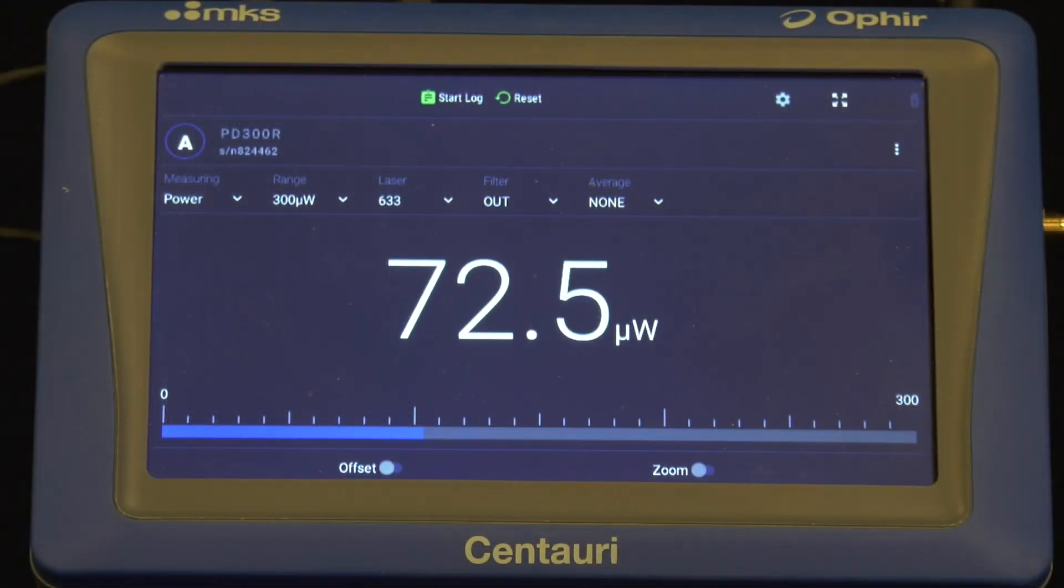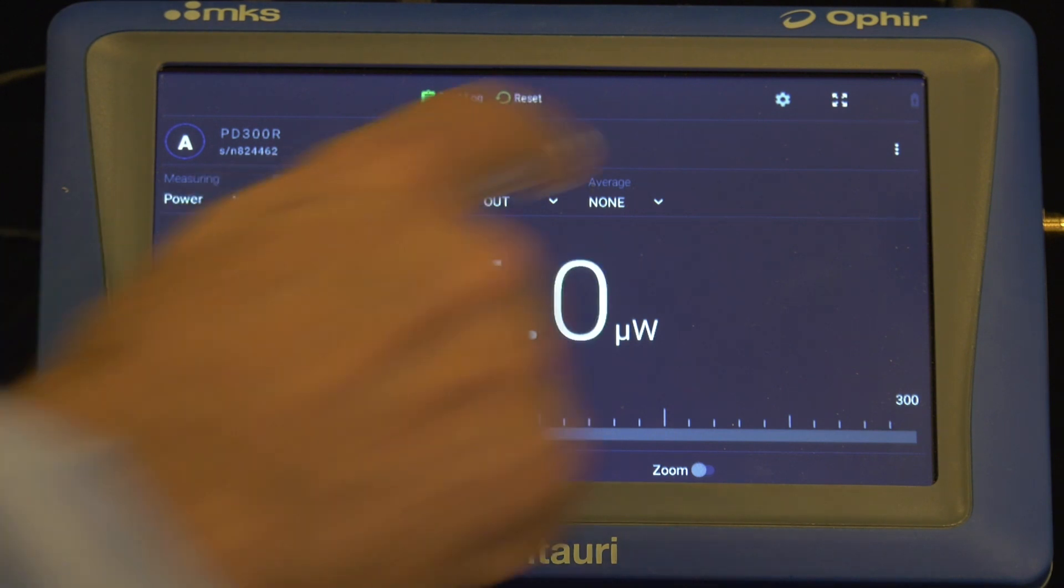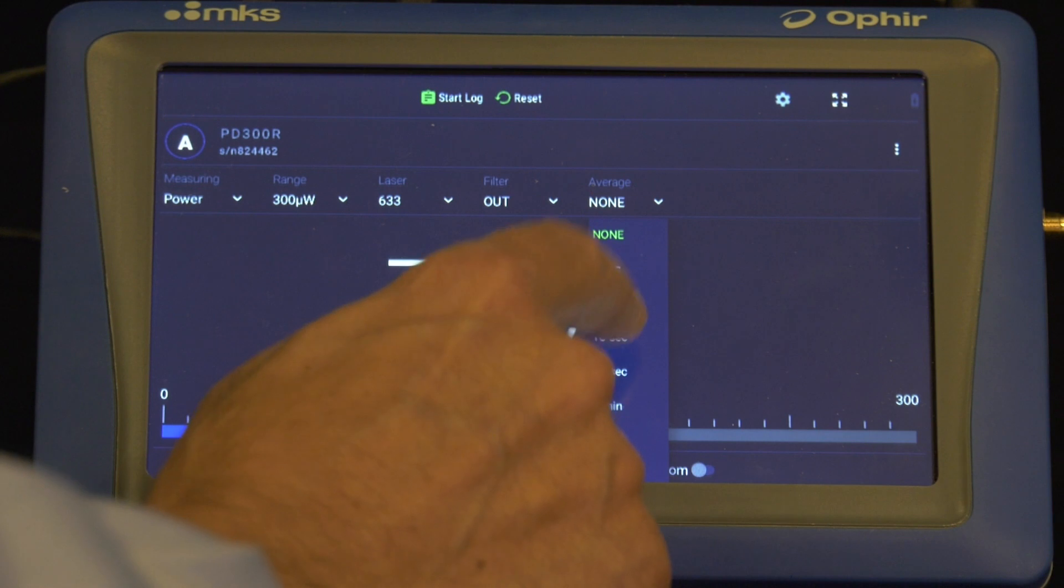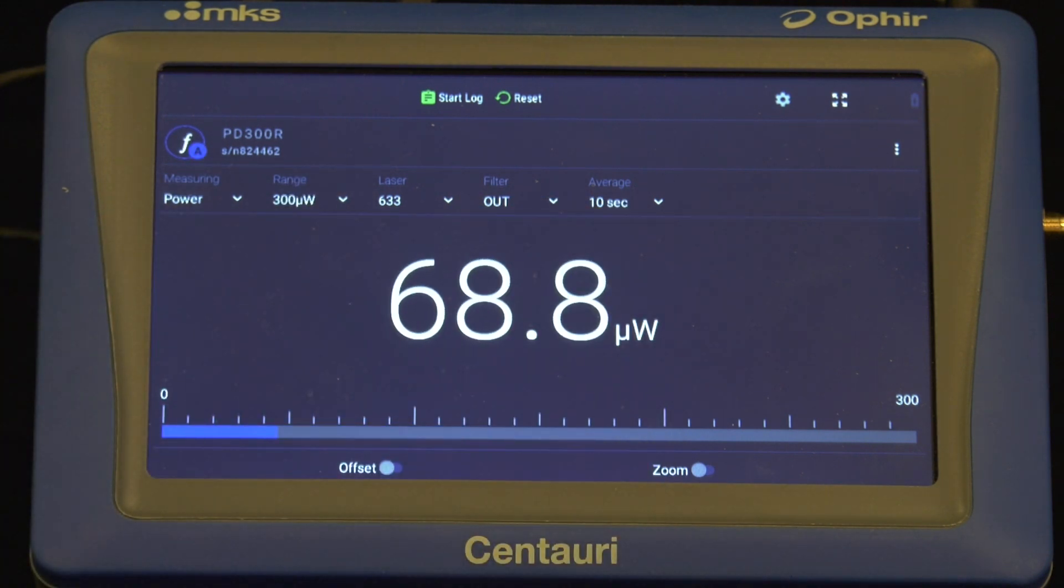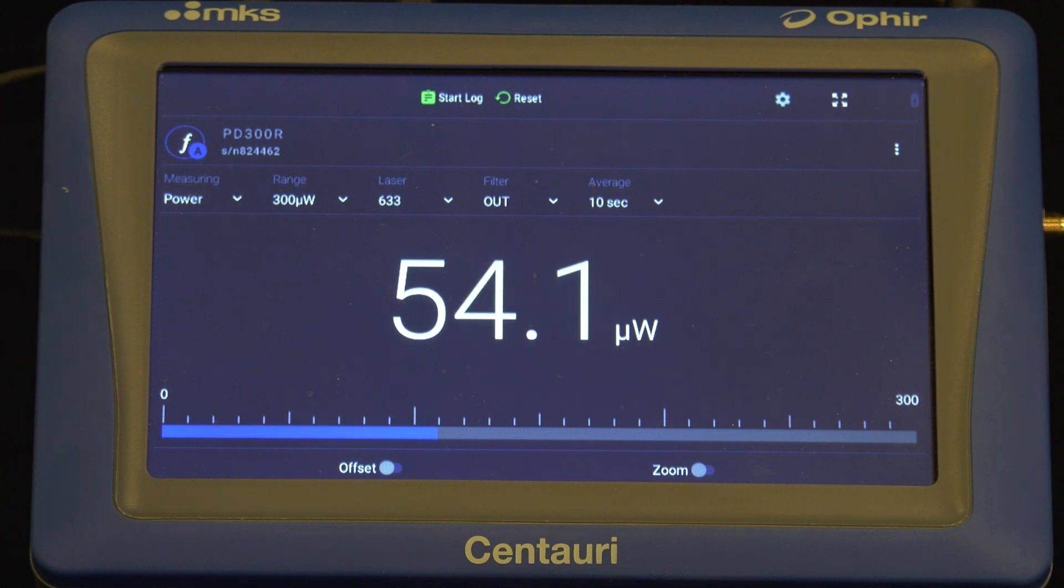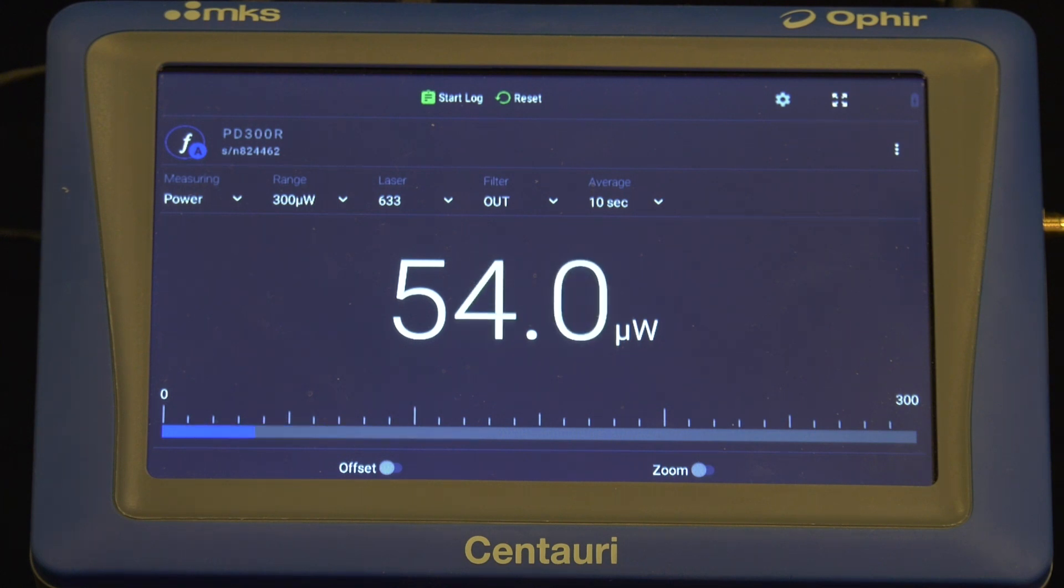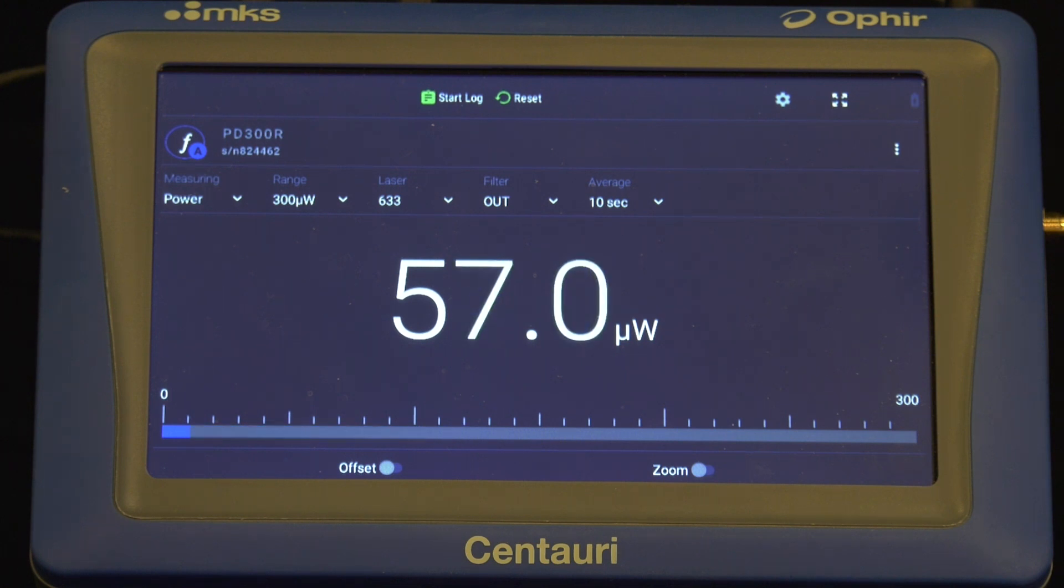One relatively simple solution for the beat frequency problem would be to use the meter's averaging function. By reading out the running average power over a time period at least as long as the beat frequency cycle, the beating gets averaged out, and the correct and stable power reading will be displayed.